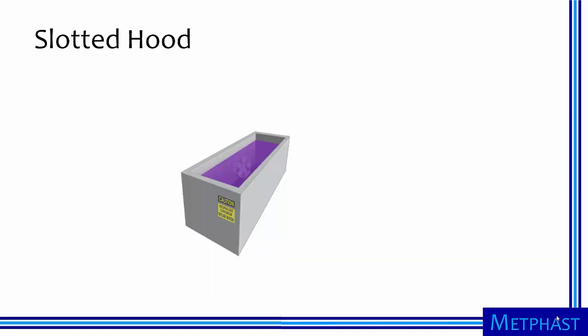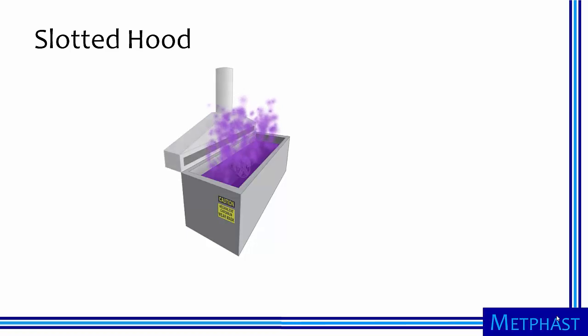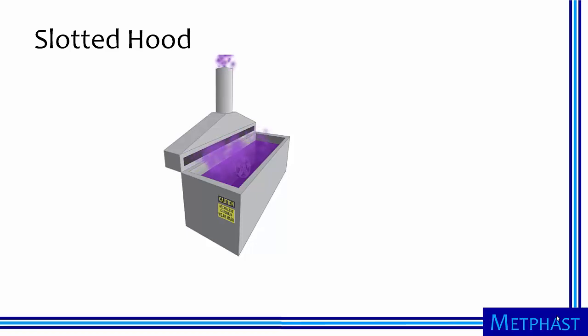The slotted hood is a special type of capturing hood. Often, slotted hoods are used to ventilate tanks. In this tank, hexavalent chromium is being used to plate chrome onto the wheels of a car, producing highly toxic vapors. A slotted hood can be used to capture these vapors. The slot ensures that air velocity is sufficient over the entire surface of the tank for good capture.